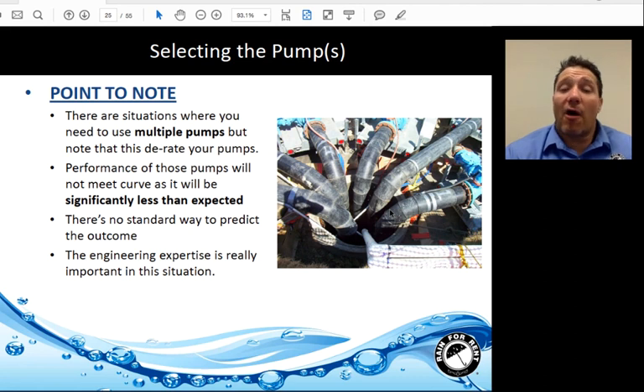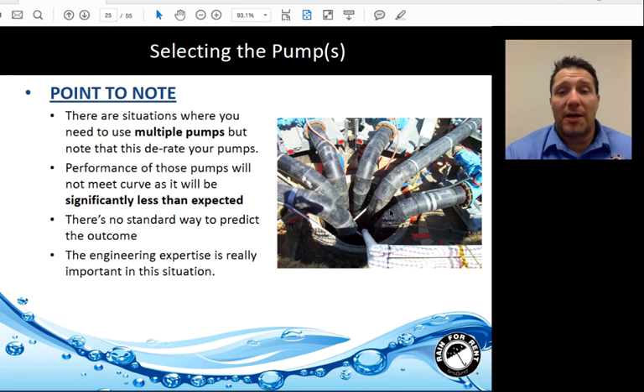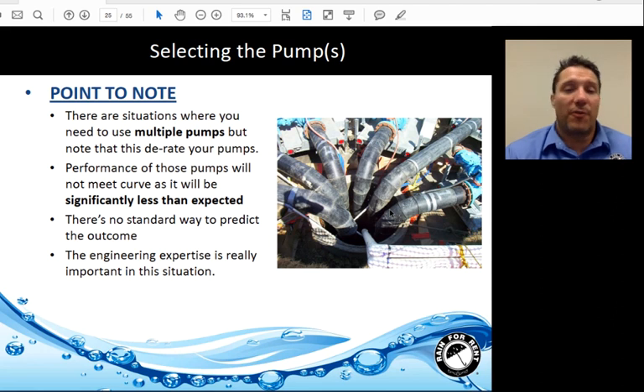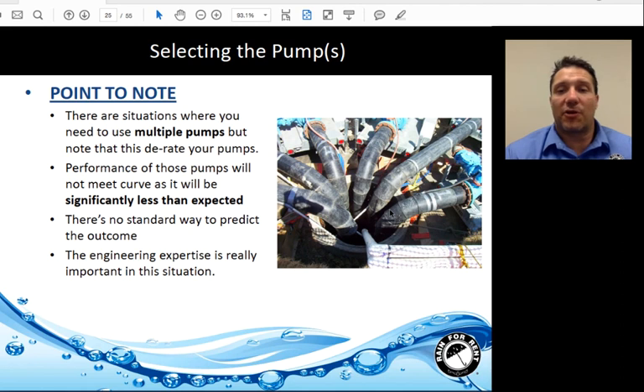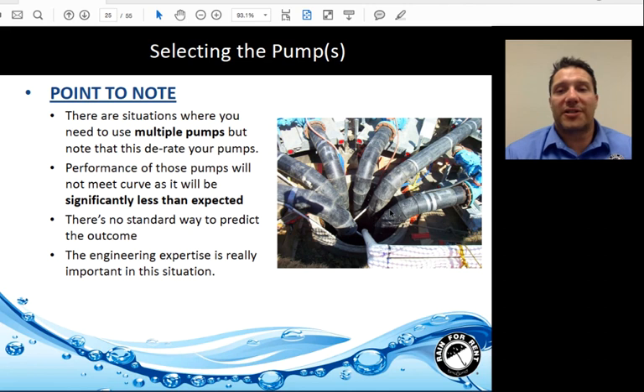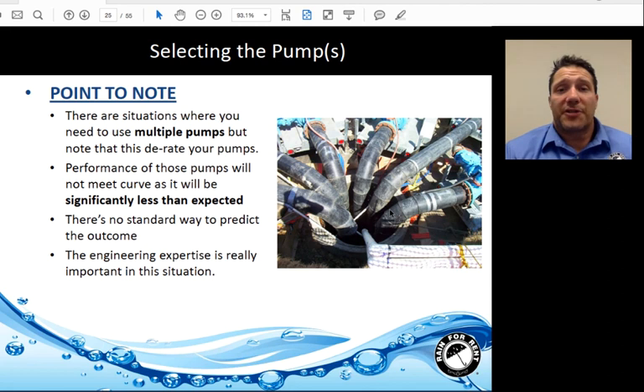There are situations where you use multiple pumps in one manhole. However, depending on how many pumps and how close their suction stingers are, you may need to de-rate the pumps — their performance won't meet the curves because the suction stingers are so close together and the pumps fight each other. There's no standard way to predict how much performance decrease will result, so engineers should be consulted for projects with multiple suction stingers in close proximity.